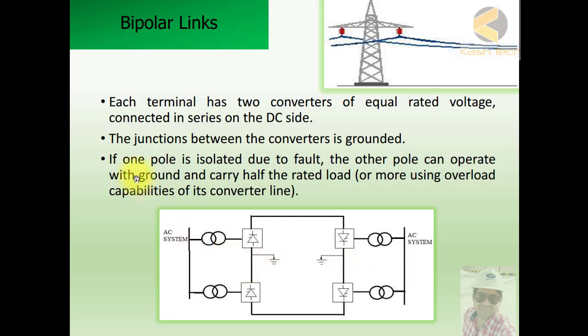The junction between converters is grounded. This is the ground. If one pole is isolated due to fault, for example this pole is isolated, the other pole can operate with ground and carry half the rated load or more using overload capabilities of its converter line.